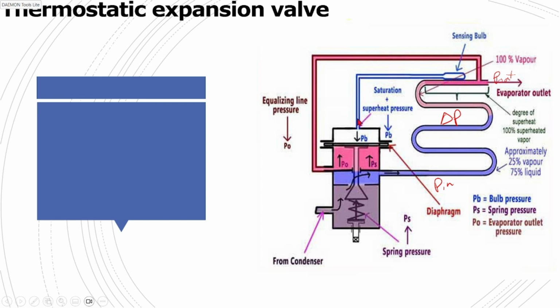The valve gets expanded and starts to move open, and the refrigerant flow starts to increase. In the previous case, as the flow increases, it acts on the diaphragm to close the valve. But here that is not the case, because the vapor has to move around the evaporator and reach the outlet. Only then will that pressure act on the diaphragm as a negative feedback.